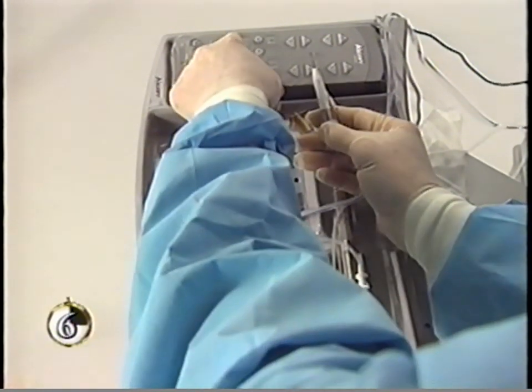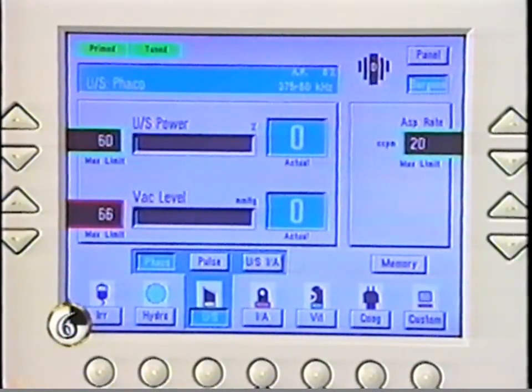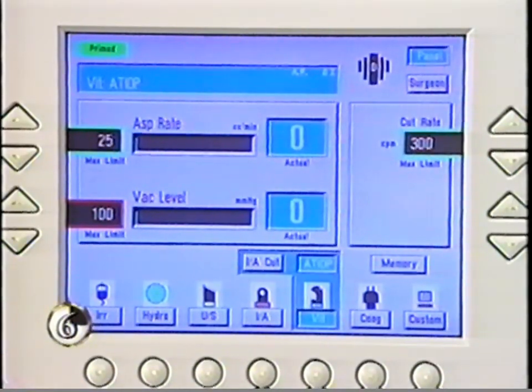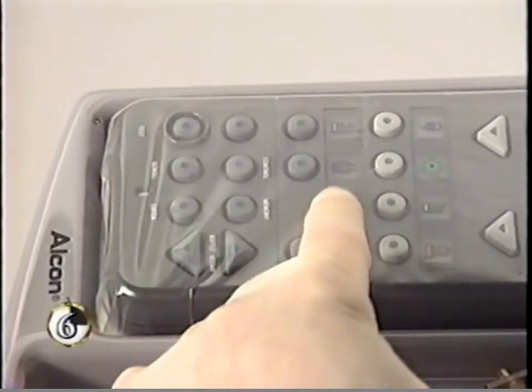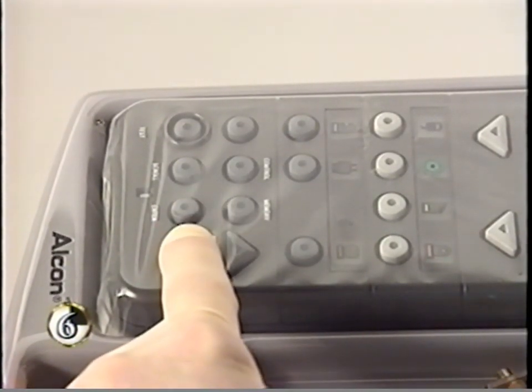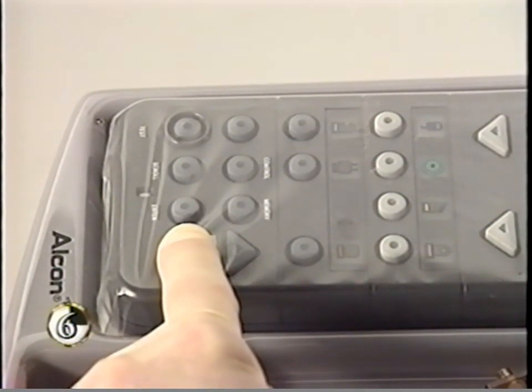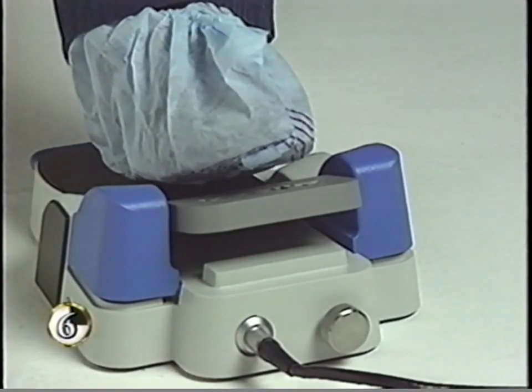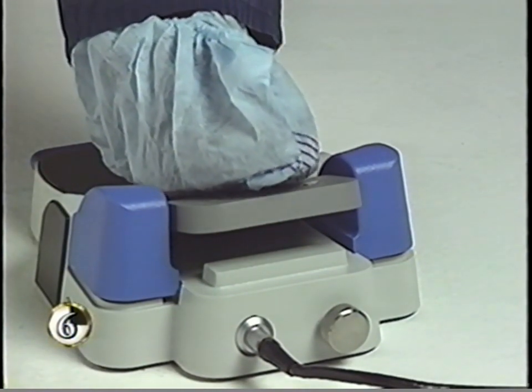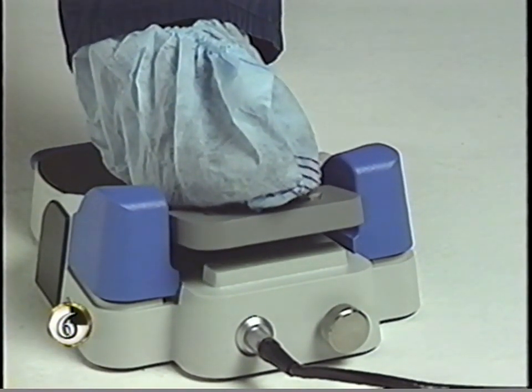Press the VIT mode selection button. You should see this display on the front panel. Select the sub-mode you wish to use. Lower irrigation bottle height to 15 to 20 centimeters. Depress the foot switch pedal to position 1 until irrigation fluid fills the test chamber.